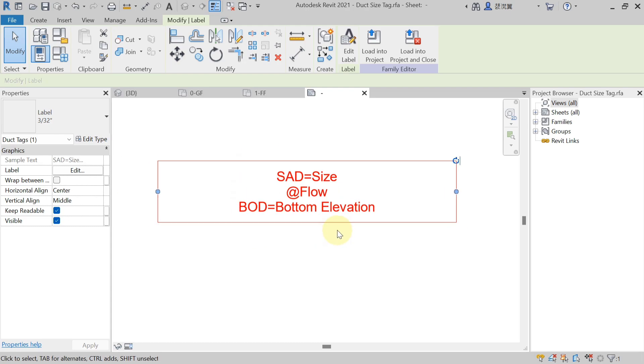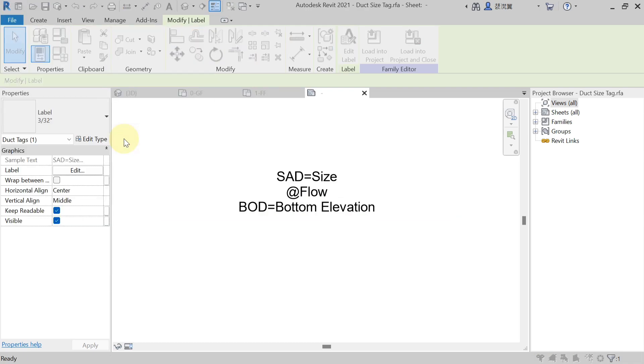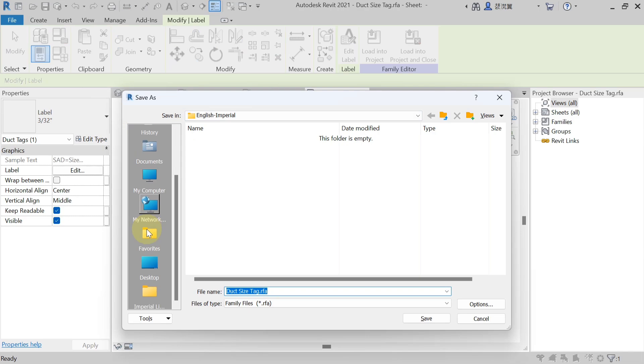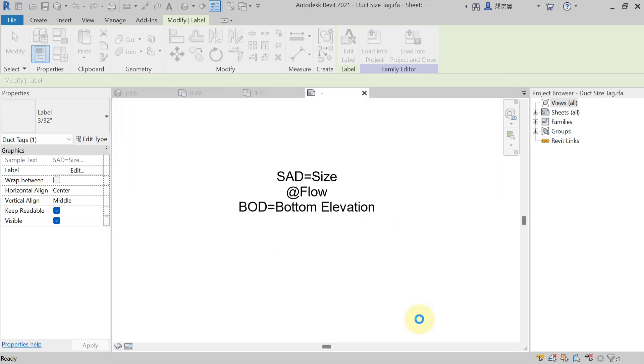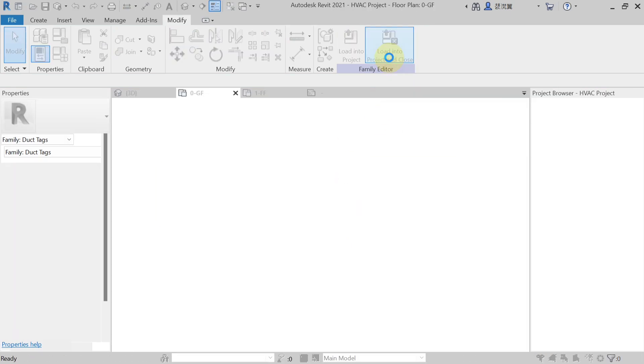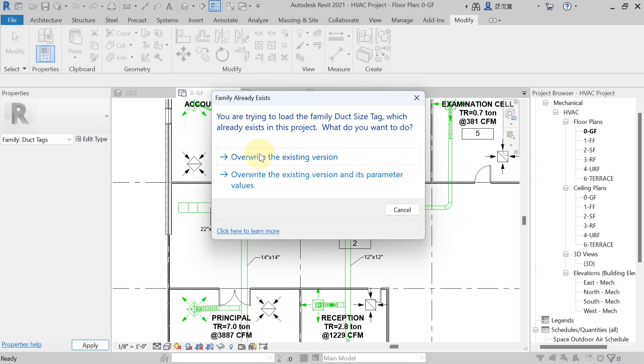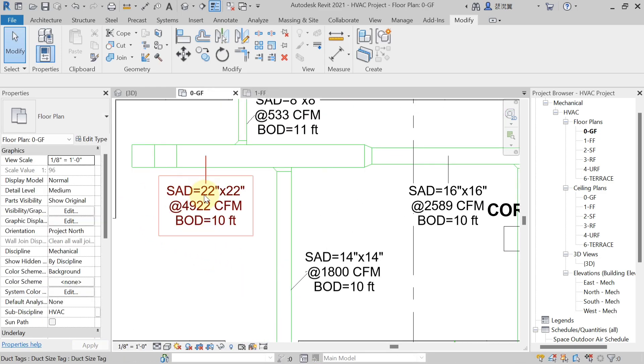After doing this setting, go to the File tab and save it as a family — Save As Family. Save it to your desired location, for example the desktop, with a name like 'Duct Size Tag'. After saving, hit Load into Project and Close. Finally, hit Overwrite the Existing. The tag will now change — you will see 'SAD=' with the size, '@rate' with the flow in CFM, and bottom of duct elevation is also showing.